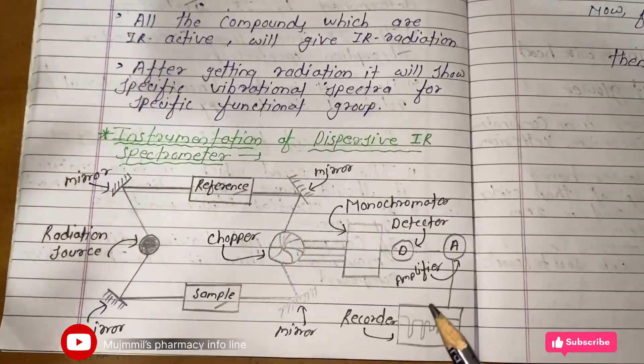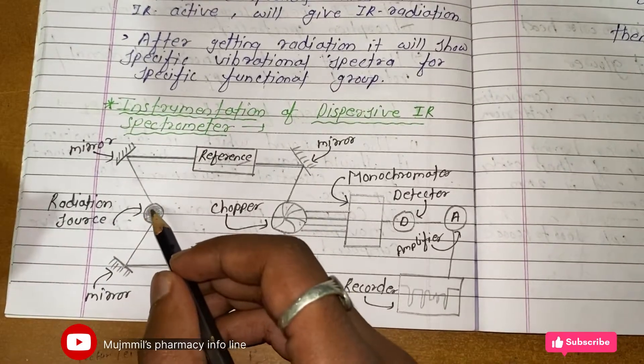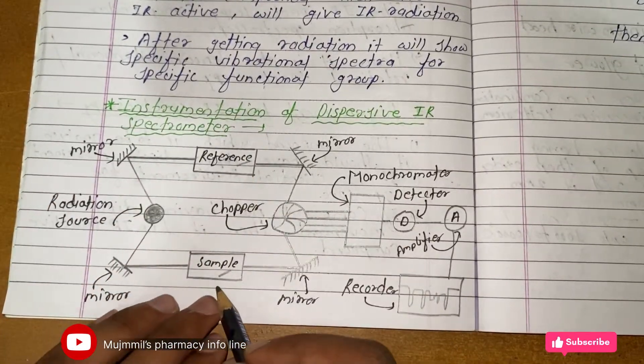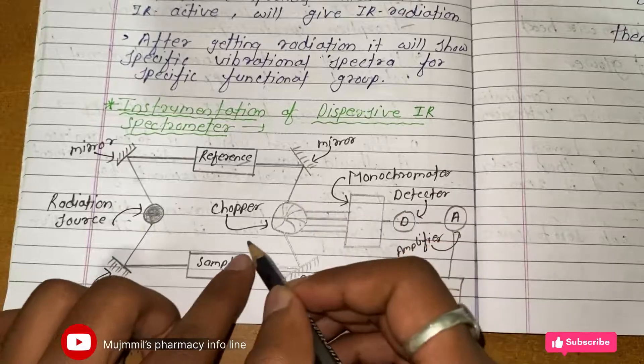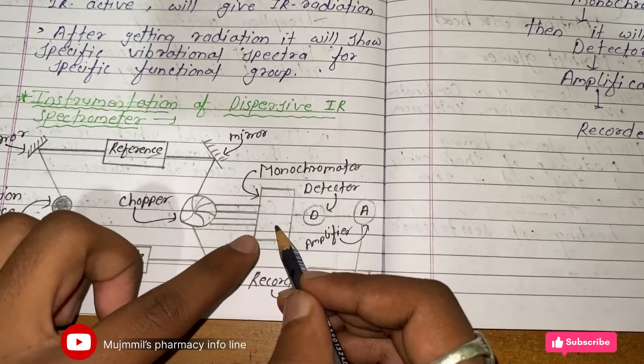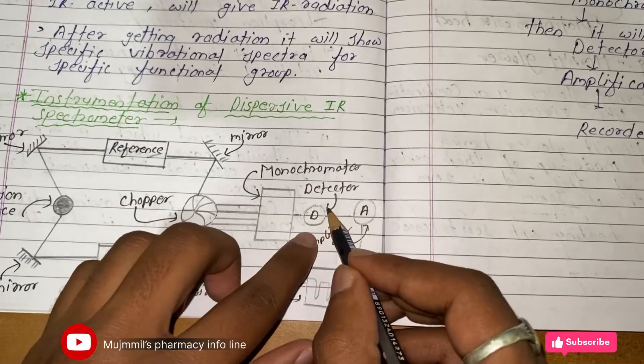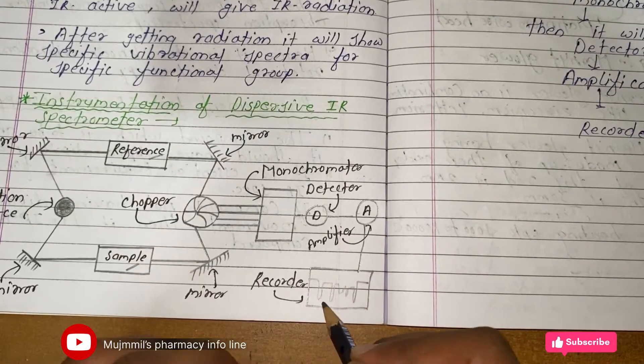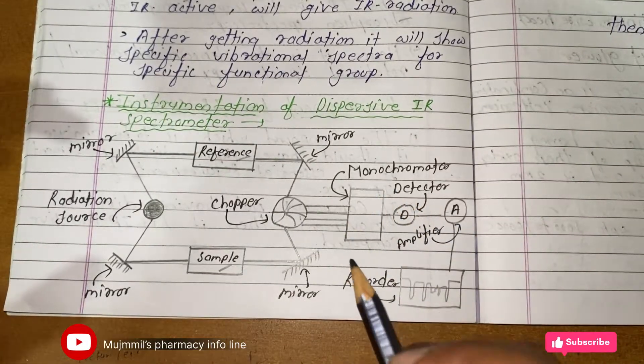Let's see the instrumentation of dispersive IR spectroscopy. From the radiation source, the light beam goes to two mirrors and is reflected into two beams — one beam goes to the reference and the second beam goes to the sample. These beams reflect from mirrors and go to the chopper, then to the monochromator, where polychromatic light is converted into monochromatic light. From there it goes to the detector, where light energy is converted into electrical signals. The signals are amplified and the final response is recorded.